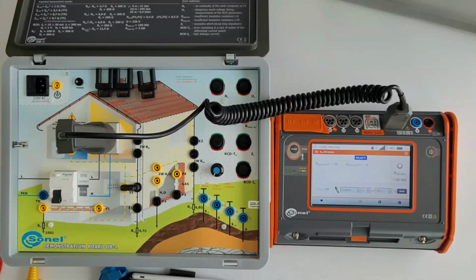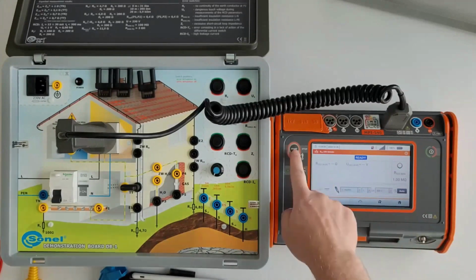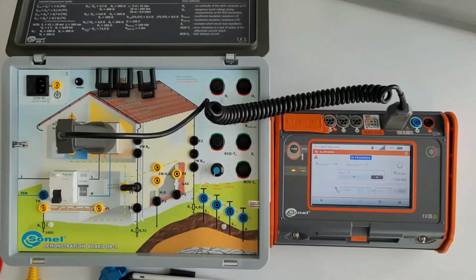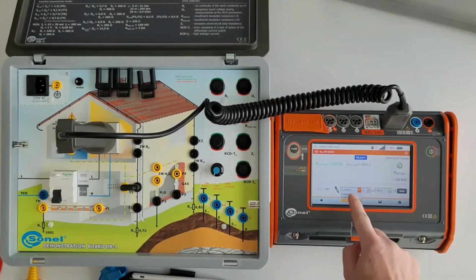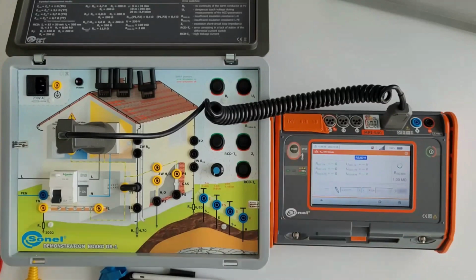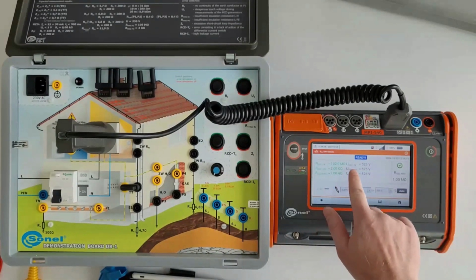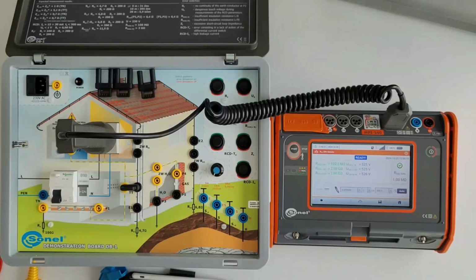This is the way we short-circuit live and neutral, live and neutral wire, and check the insulation resistance to the protective wire. And now I will check the resistance between live and neutral, live and protective, and neutral and protective. If you measure insulation resistance in this way, you can see that the live-neutral value is less.